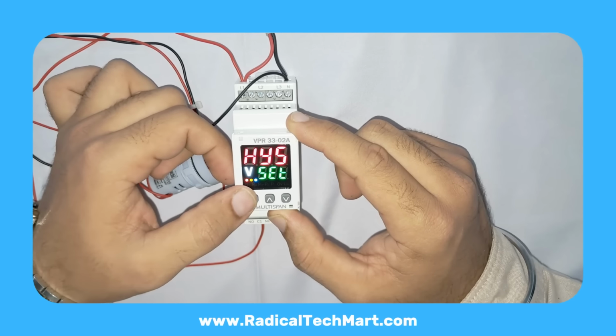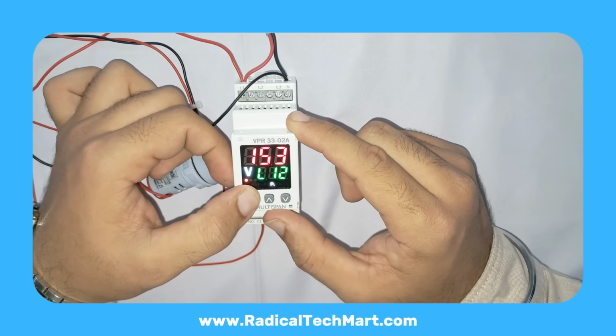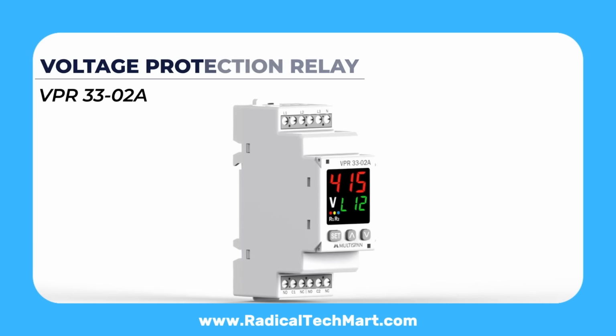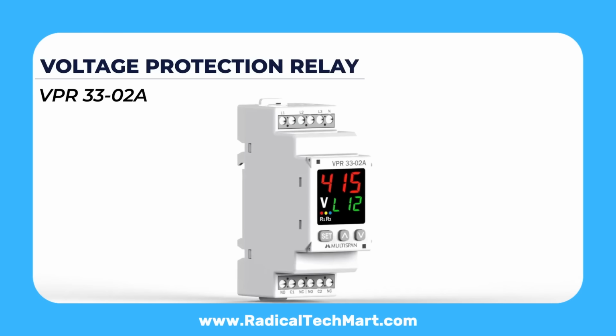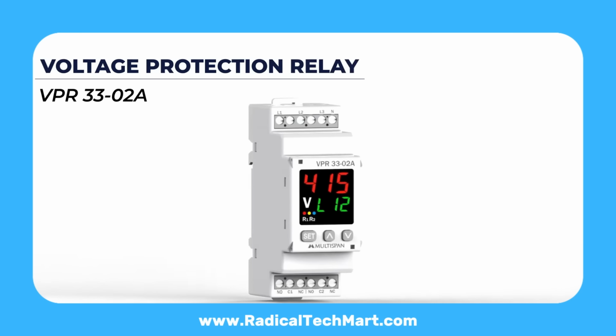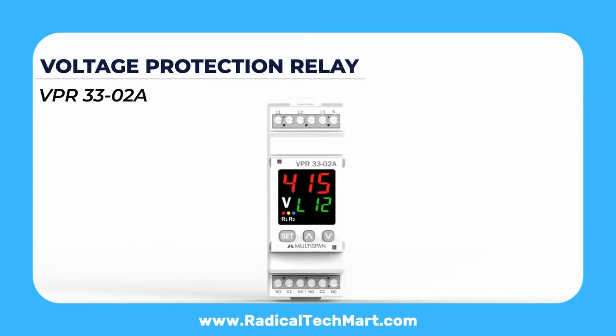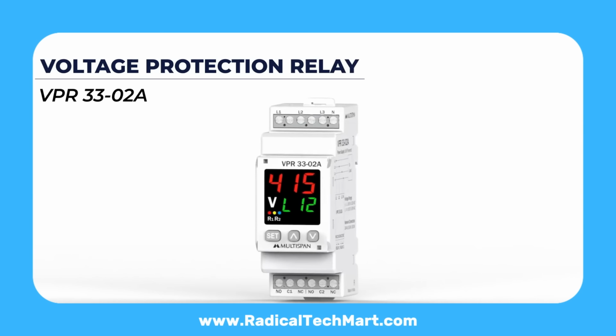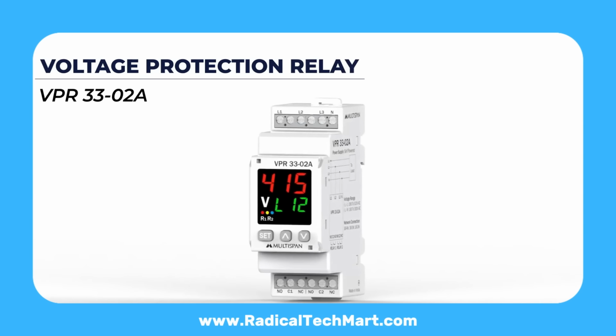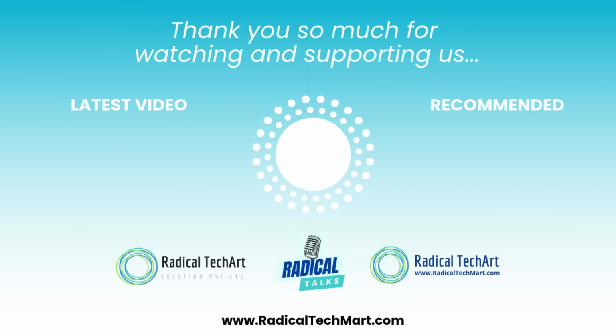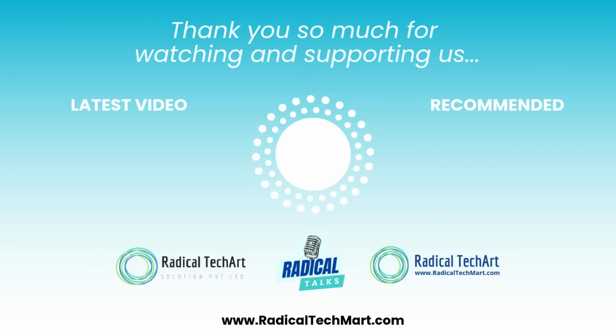After all settings are done, press and hold Set to exit the parameter menu. So this is how you wire and configure the VPR-33-02A voltage protection relay. Set over and under voltage. Configure frequency protection. Adjust delays, hysteresis, and use auto or manual reset for reliable protection of your single-phase and three-phase systems. Thank you.